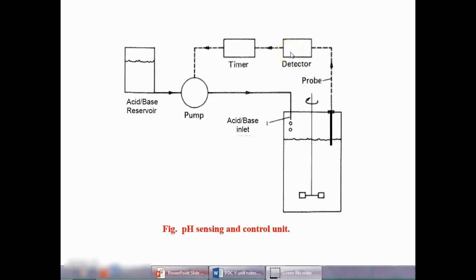For different pH values, we will have different currents. Based on the current strength or signal, it will determine the actual pH present in the fermentation process. Then it will compare that value with the required set point. If any deviation is detected, immediately it will activate the pump.